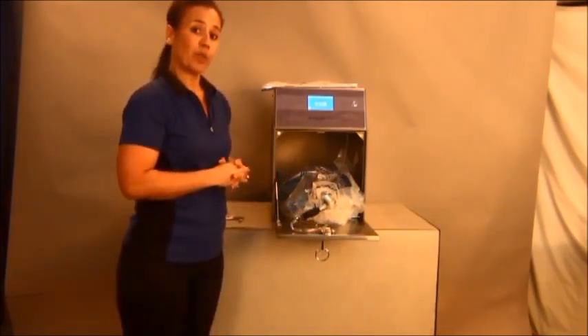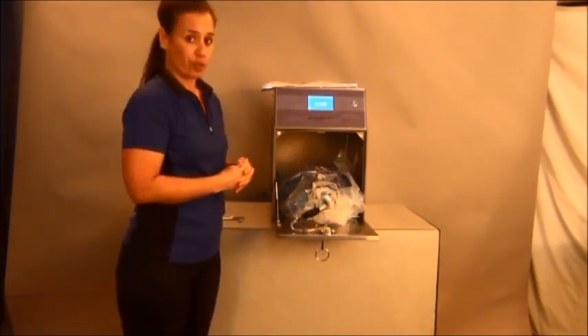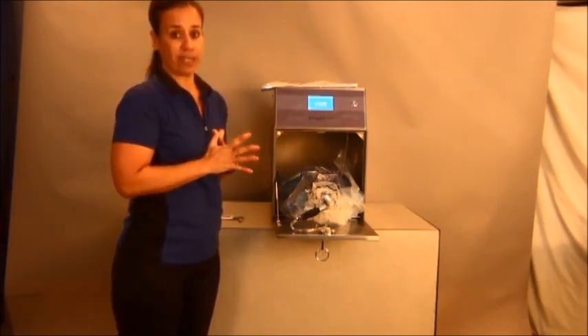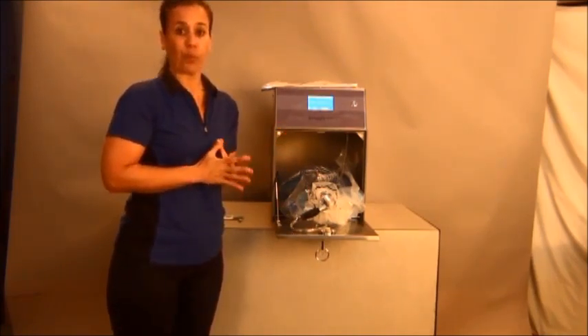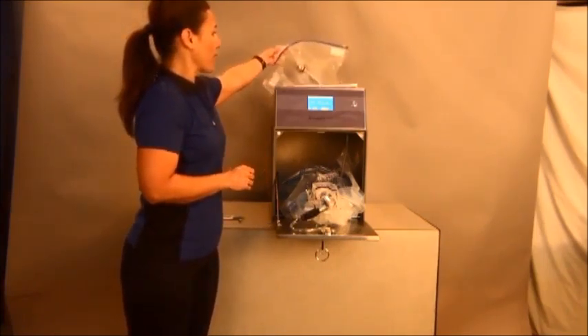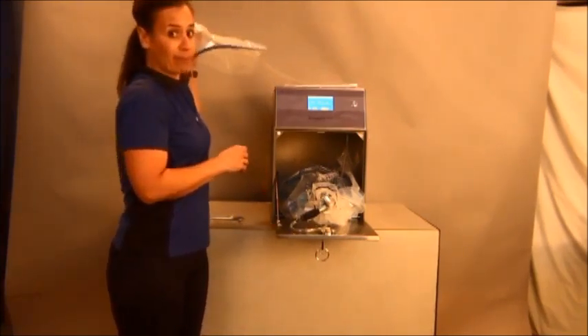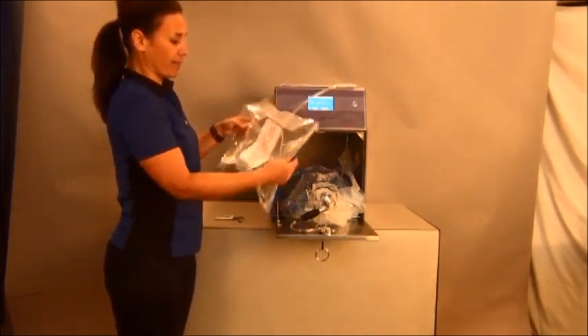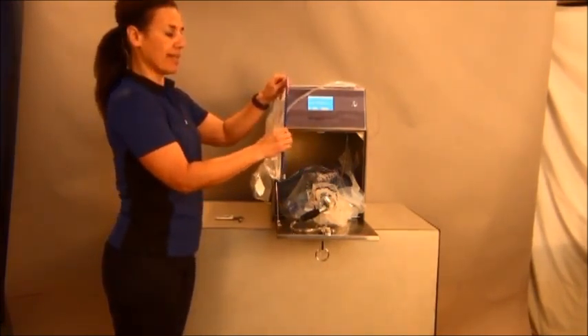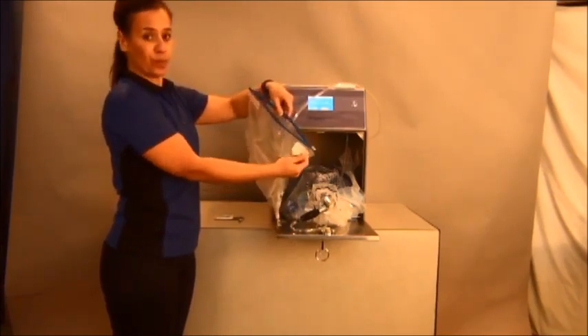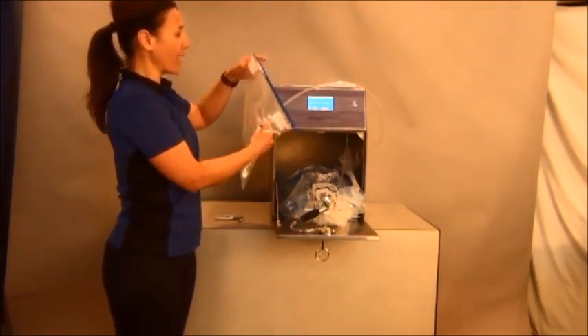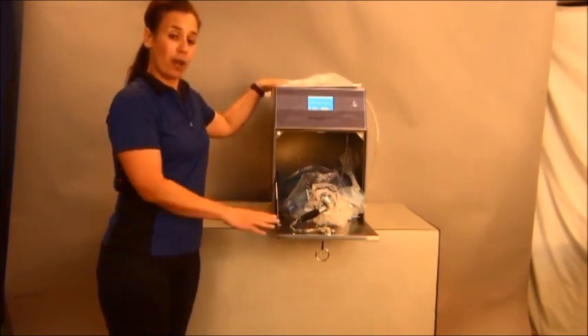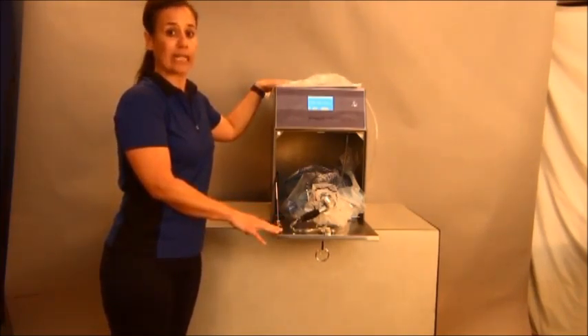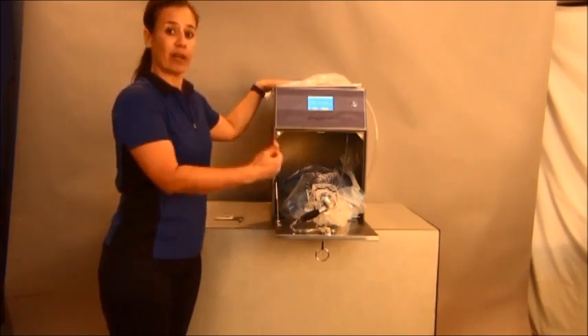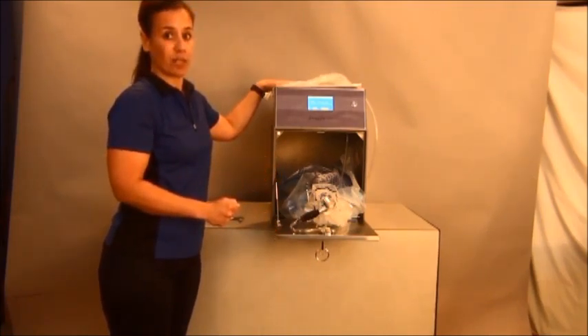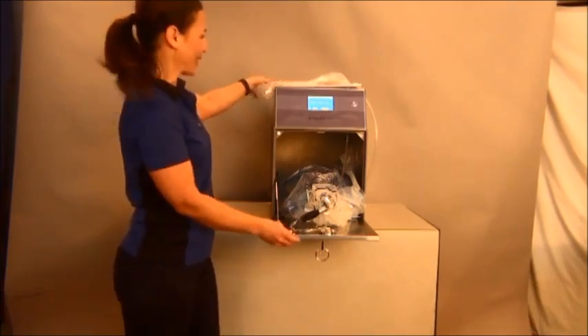If at any point in time you inadvertently drop a gas cartridge and it is activated outside of the sterilizer, immediately stop whatever you are doing and place the cartridge into your emergency containment bag located here on the side. It is a zipper bag. You place it into the pouch, close the pouch, and then follow the standard operating procedures for your hospital or clinic, which may entail leaving the area in which the sterilizer is located.